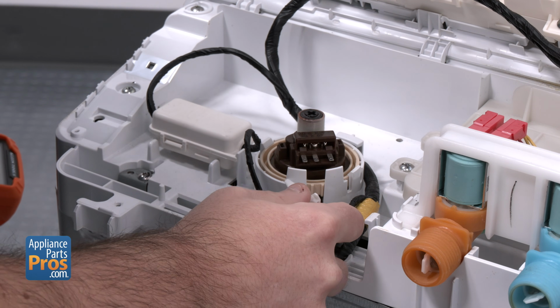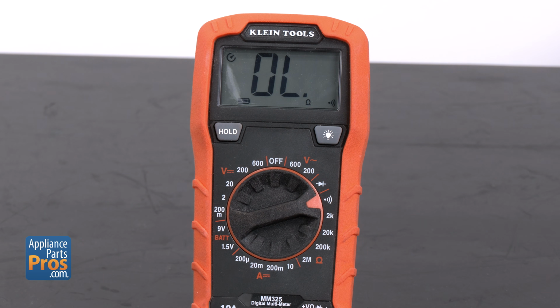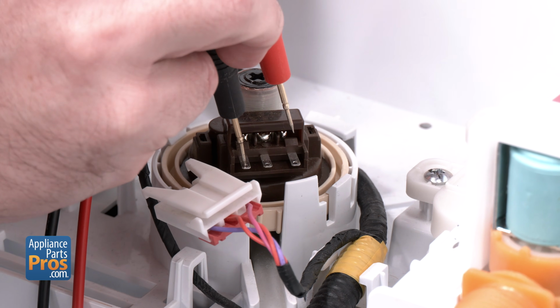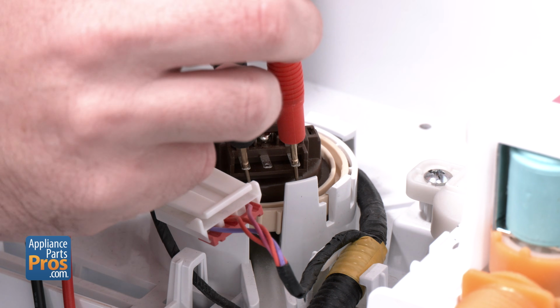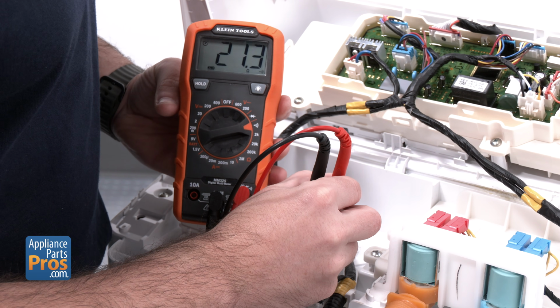Disconnect the wires from the pressure sensor. Set your multimeter to resistance or ohms, indicated by the upside down horseshoe symbol. Place one probe on the violet wire terminal and the other on the pink wire terminal. You should see around 21 ohms.